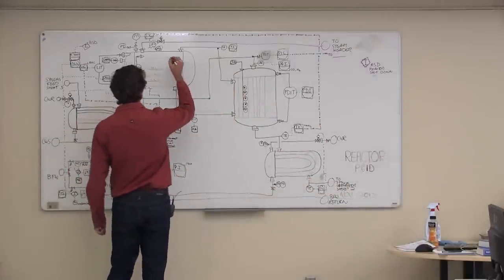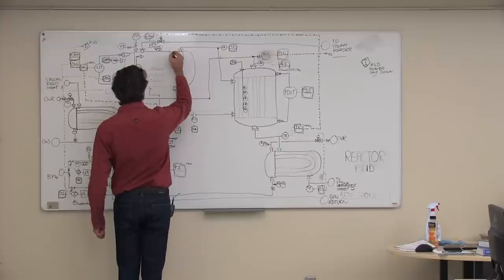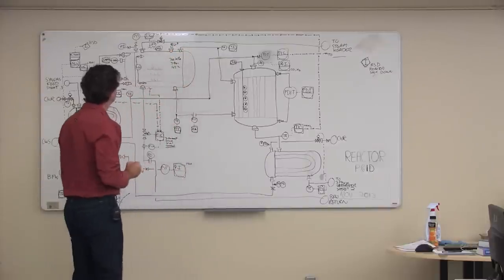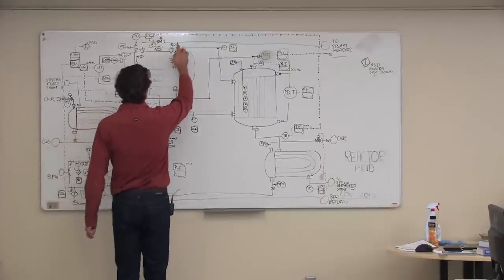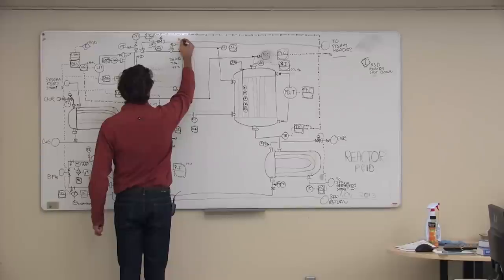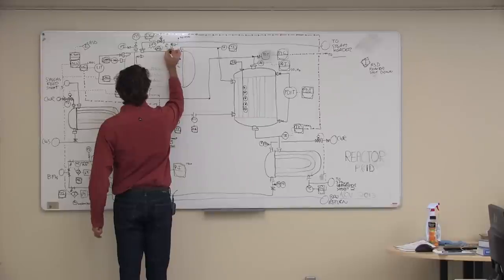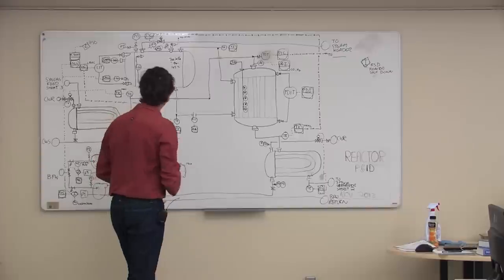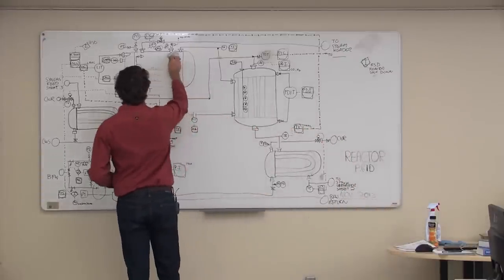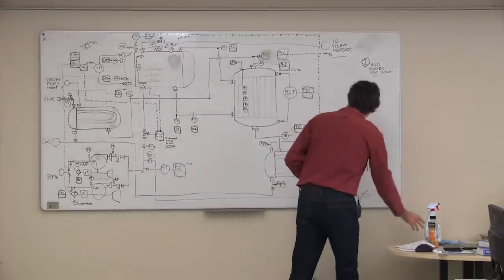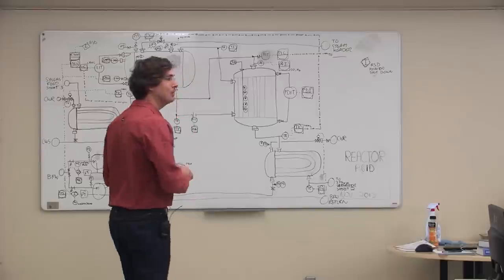We also need relief valves — we've got a potential pressure hazard here. Put a relief valve on the steam drum going to atmosphere, not into the steam line, set at whatever the set pressure is.